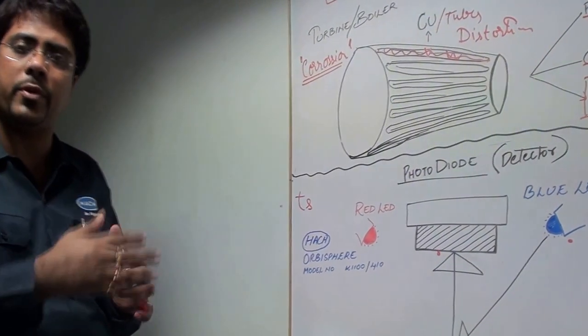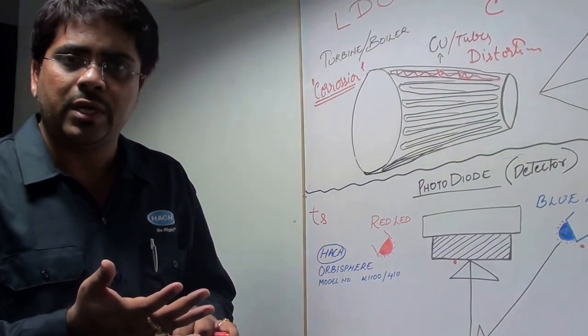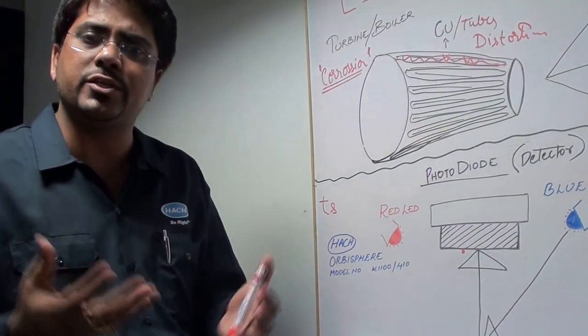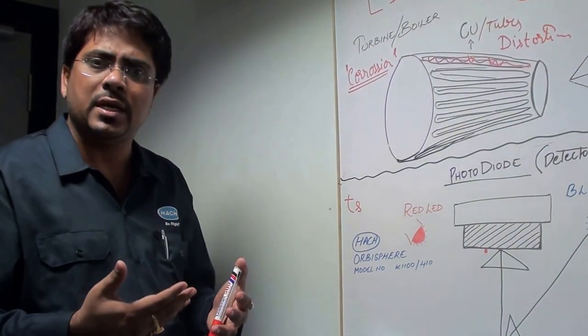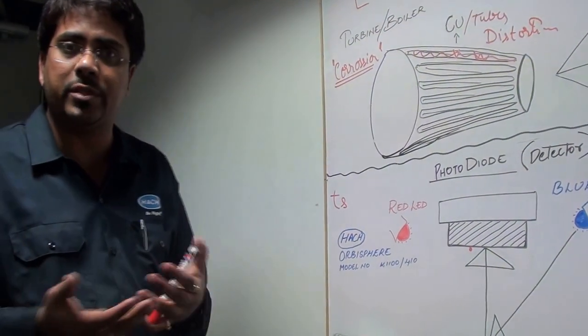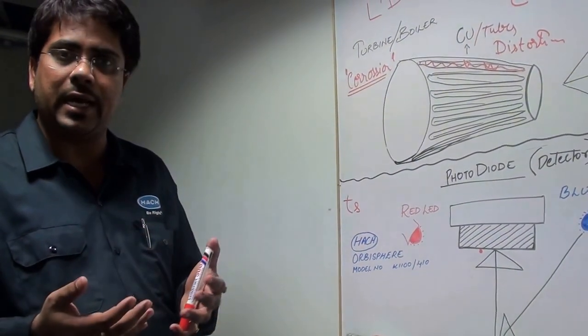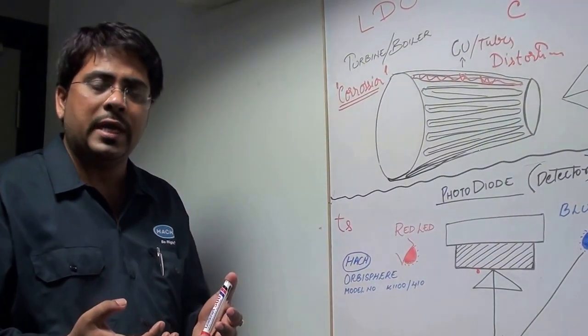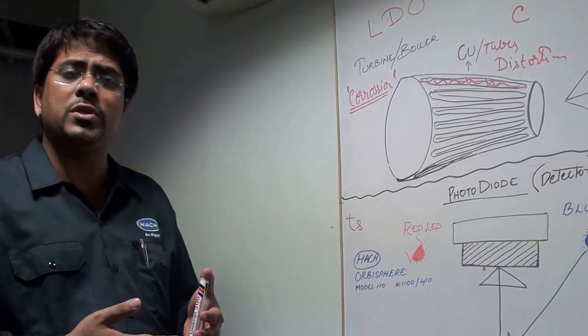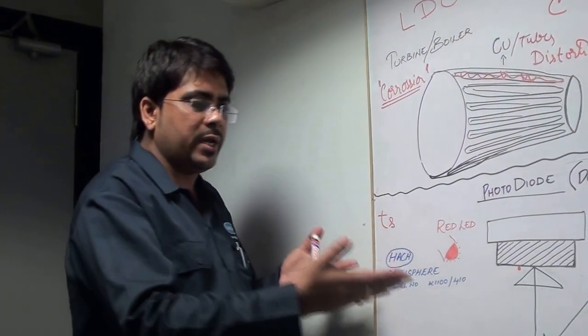What are the basic components of luminescent dissolved oxygen analyzer? We are eliminating all the old problems of the existing amperometry technology. The root cause problems were the repetitive change of membranes which get punctured with use, change of refillable solutions, and change of O-rings. There are a lot of spares and consumables that need to be changed every quarter or every half year. The most important issue is the stability time or polarization effect. When you install a probe in the old technology, it takes more than 8 to 10 hours to get a stable reading on the display.